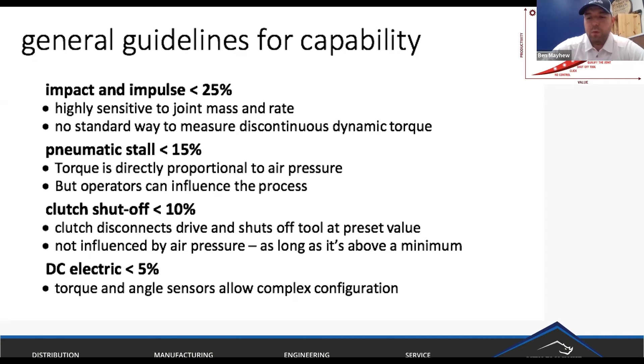They don't leave our repair and calibrations department as a direct drive DC tool unless they're within 2% of target. So these tools can be extremely accurate if that's what's needed, but if that's not what's needed, then maybe we need to look at a different tool.